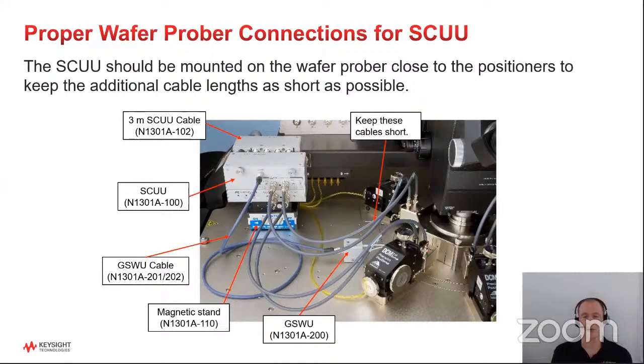And then, as I said, you want to keep the cables going off of that SCUU as short as possible, because those are the cables you actually have to compensate for with your open short or potentially load calibration. But this arrangement allows you to keep those cables short. And you can also see that you can mount the guard switch unit if you want to use that as well, which we do recommend. You can mount that on there as well and feed that into your wafer prober so that those are shorted. And again, this creates a nice, complete, very easy to use solution for making CV and IV measurements on wafer.